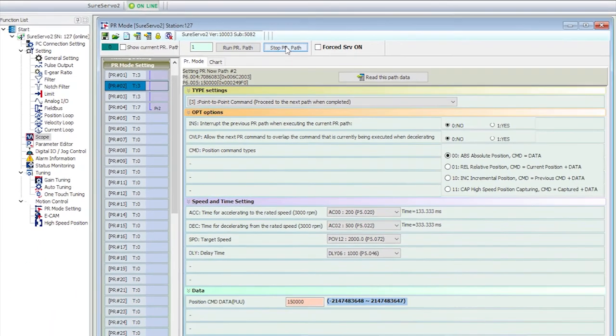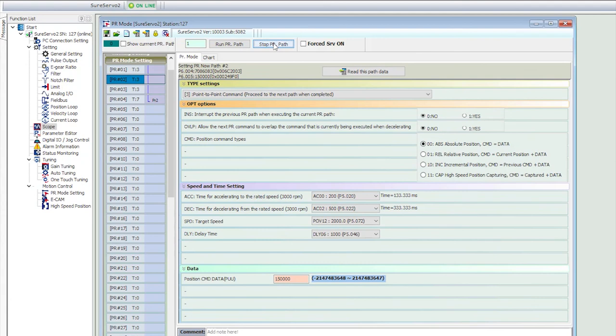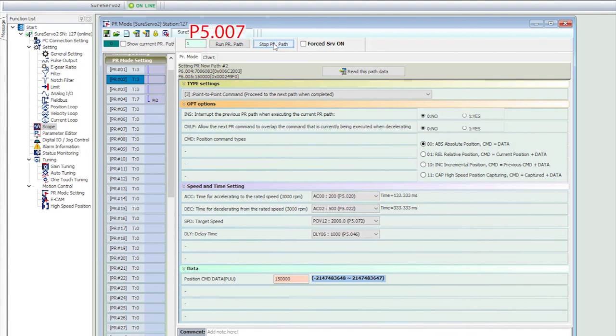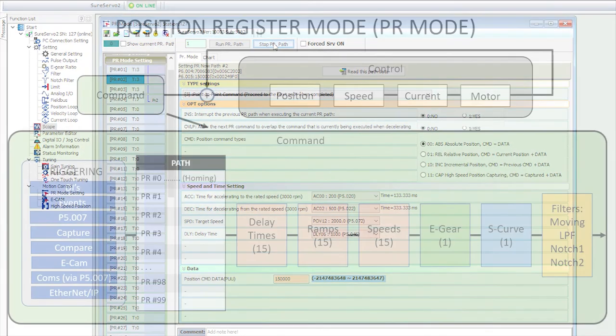That's the basics of setting up and testing paths using a manual trigger. And all we really did was enable position register mode here, modified the electronic gearing here, and entered our paths here. When we hit this button, it simply took this path number and sent it to parameter 5.007 to manually start the path. We could have gone to parameter 5.007 and done that ourselves. This is just easier.